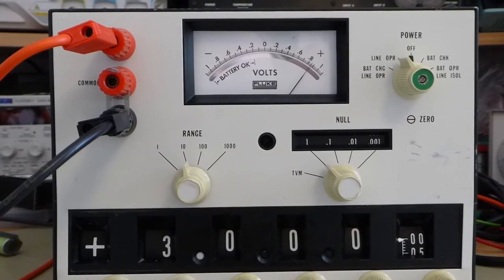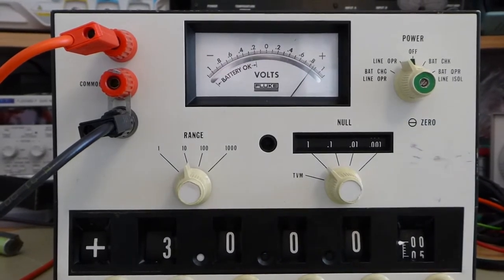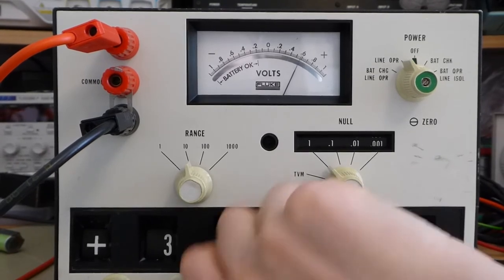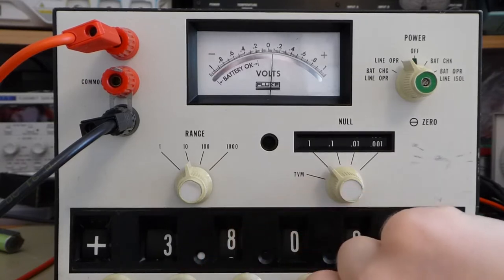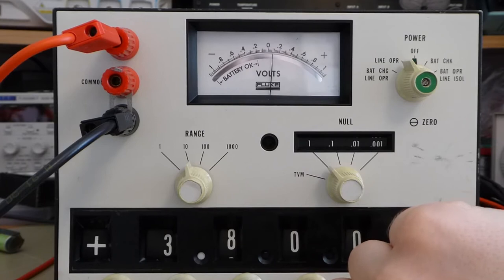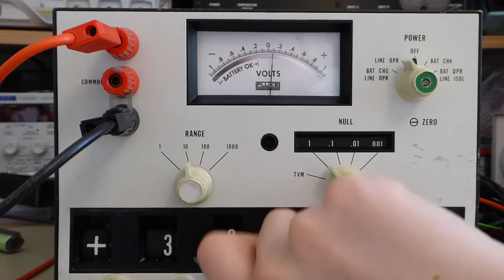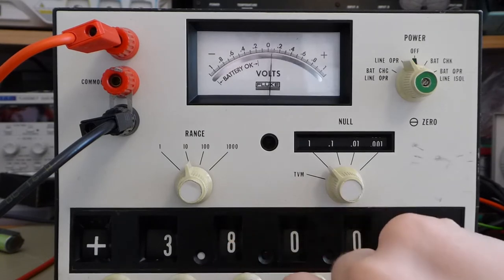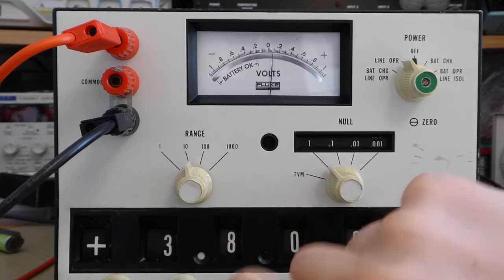I'll probably just zoom in a bit to give you a better idea of what's going on. Yeah, I think that's a bit better. Right, so the next digit, let's get rid of the 8. So let's dial in an 8 on this digit. 4, 5, 6, 7, 8. Okay. We're probably... Yeah, it's still 8. So if I went to a 9, for example, here, you can see the needle goes just below 0. So we know this digit must be an 8, not a 9.